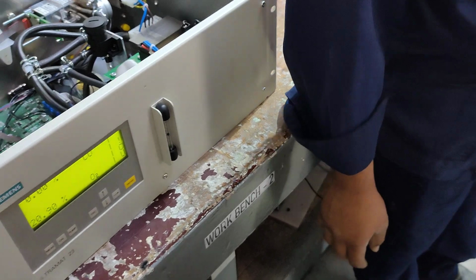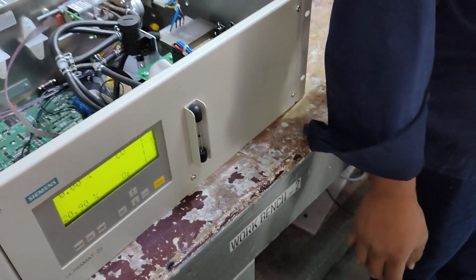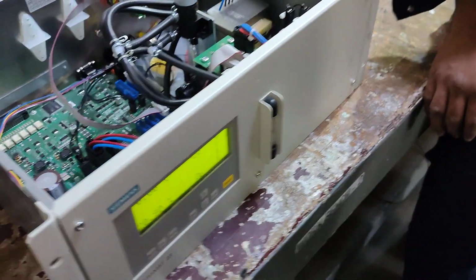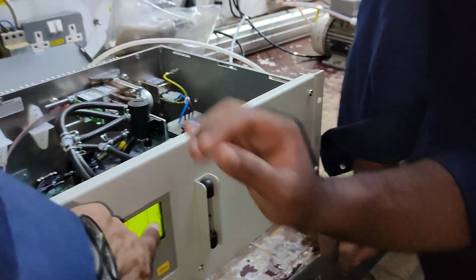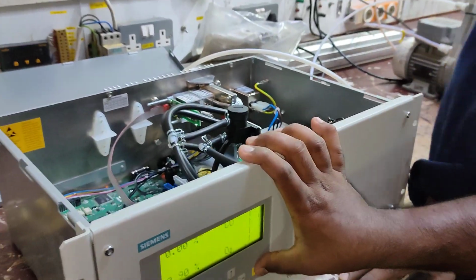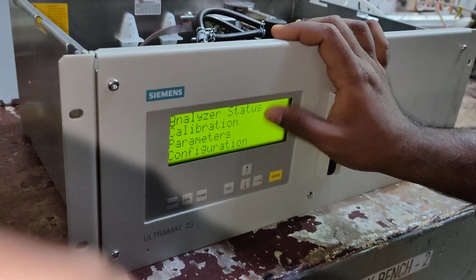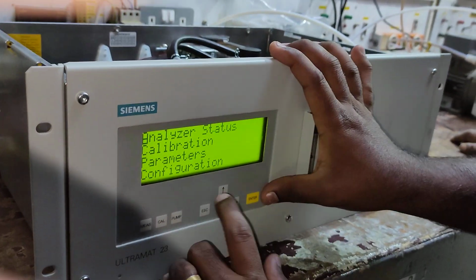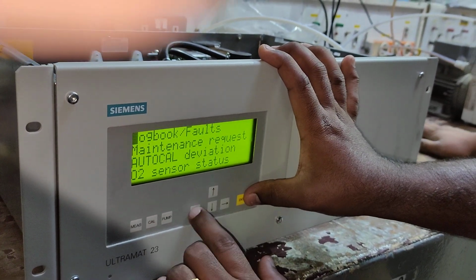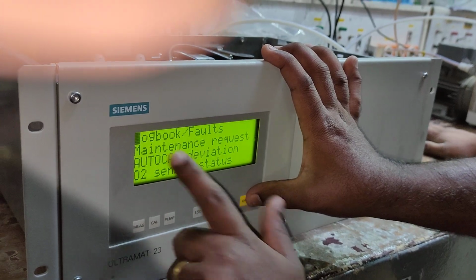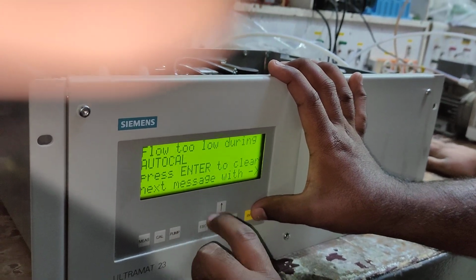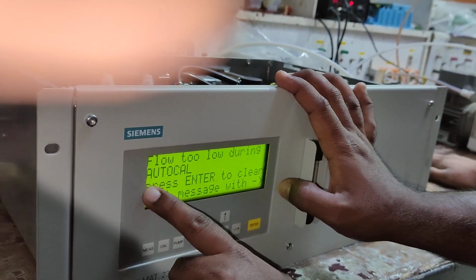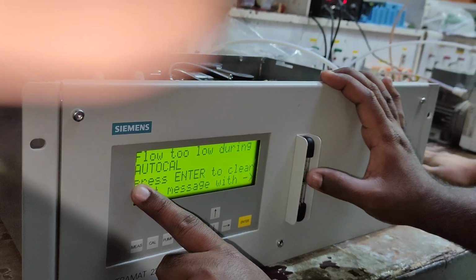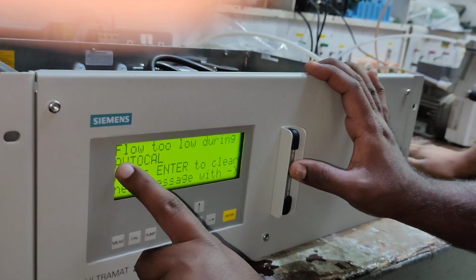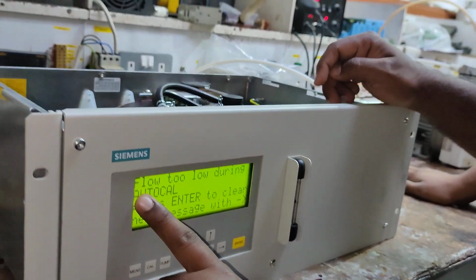Yeah, the purpose of the software is not to do calibration. The software purpose is different. If you have to download the... What is this hash mode? I'm coming to that. So you have 4 parameters here. You have analyzer status. In the analyzer status, you have status. And then you have the logbooks. The logbook says flow too low during autocal. So when we were doing the autocal at the beginning, there was no flow. Because of that, this switch has given a command to the motherboard.